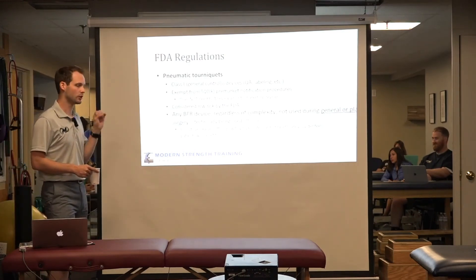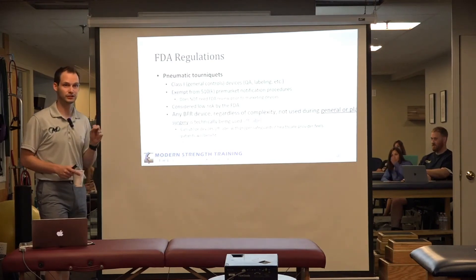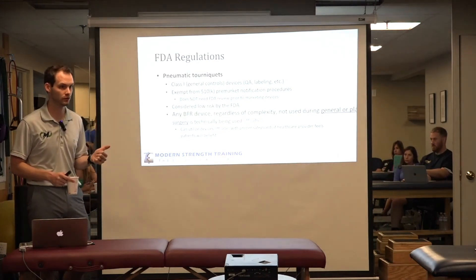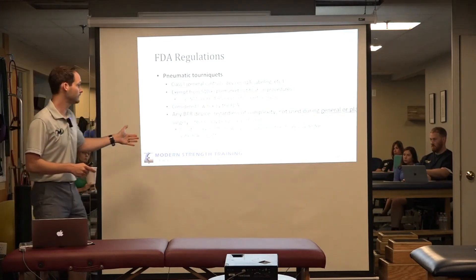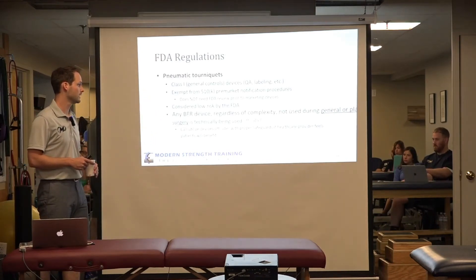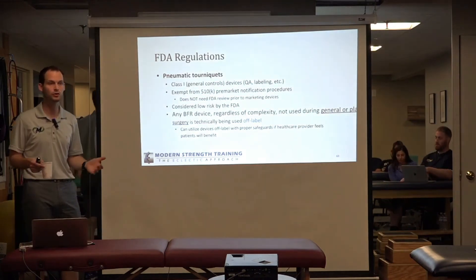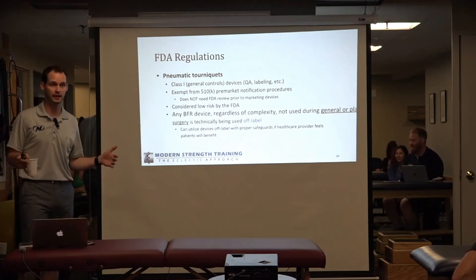We're not using BFR devices for general or plastic surgery, so technically every BFR band is considered being used off-label. You might say, oh gosh, that's not good. Well, the FDA also says that healthcare providers can utilize devices off-label with proper safeguards if the healthcare provider feels there will be some benefit. You could theoretically have BFR devices that are unregulated.